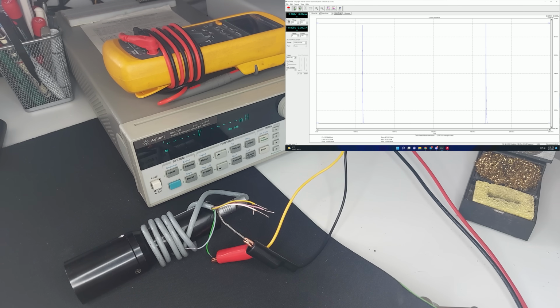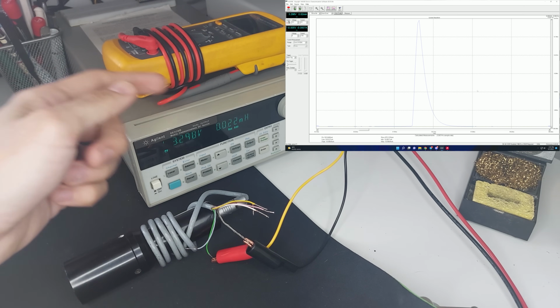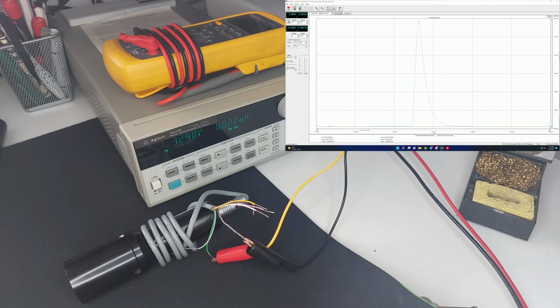Yeah, okay. So as you can see here, the peaks are basically up to the high range of the power supply. They're almost exceeding the 20 milliamp that you would have on this power supply's range. So as I said, low range is 20 milliamps with a 1 microamp resolution. High range is the full power of the power supply, but with a 100 microamp resolution.